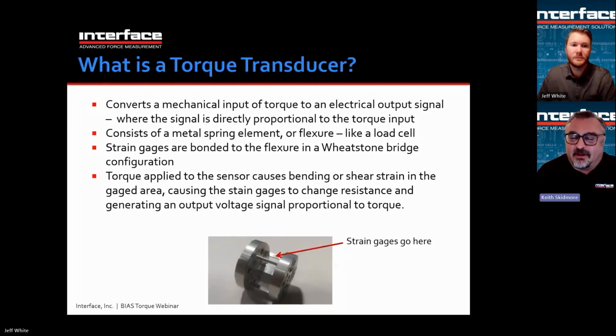So what is a torque sensor? A torque sensor converts a mechanical input of torque to an electrical output signal. The signal is directly proportional to the torque input. Basically, it's a metal spring element or flexure, just like a load cell, except it's sensitive to torque instead of force. We have foil strain gauges that are bonded to the metal flexure spring element in a Wheatstone bridge configuration. And then torque applied to the sensors causes either bending or shear strain in the gauged section, and that causes strain gauges to change resistance, which generates an output voltage signal proportional to torque.